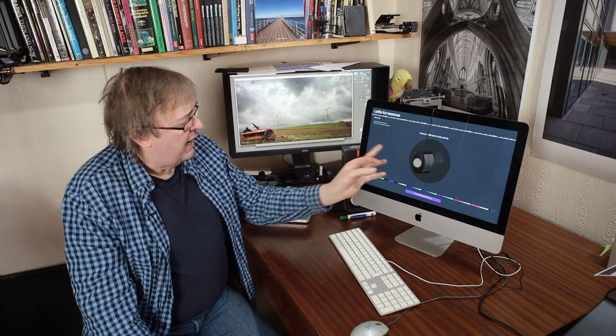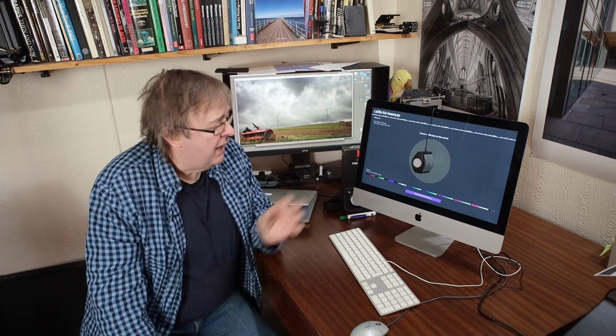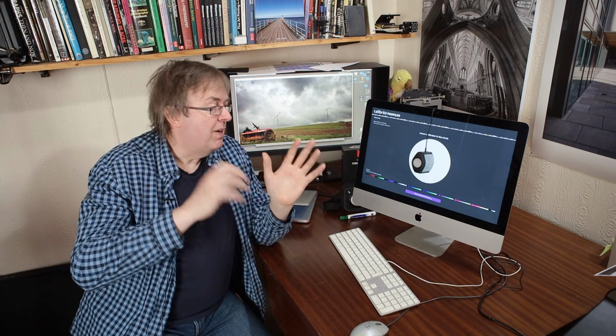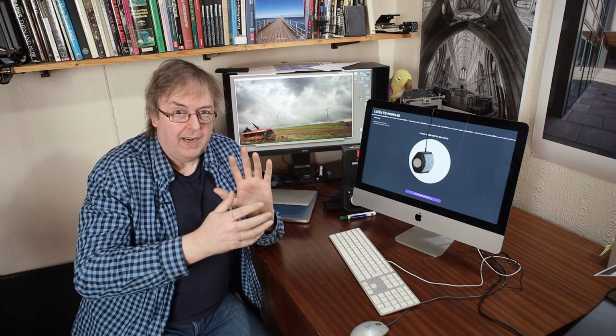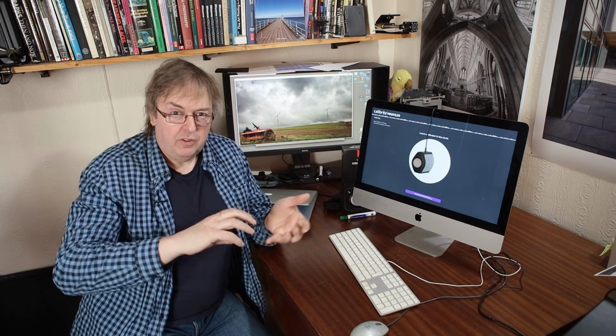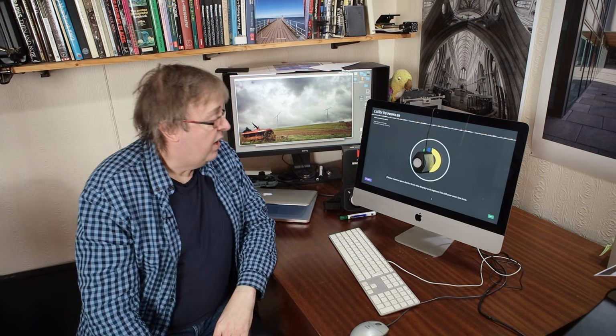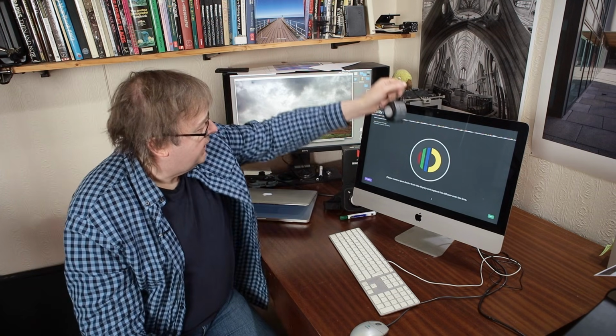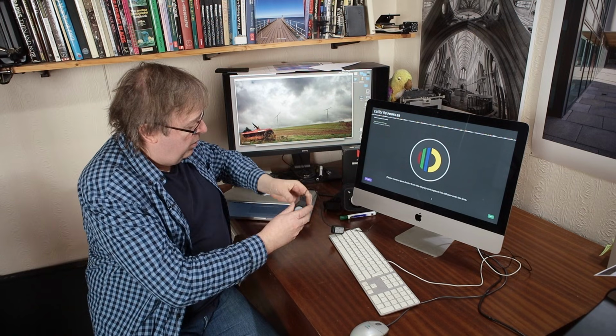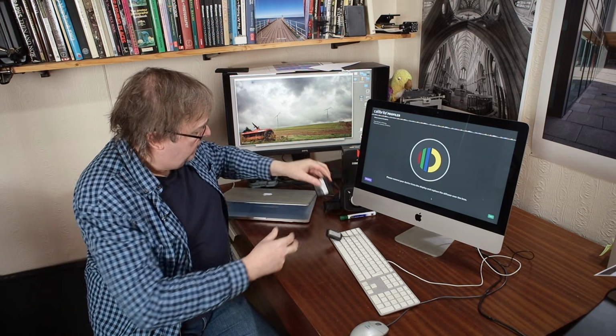Runs through, it ends off with a grayscale adjustment. Effectively, the software is displaying colours. It's then measuring what the actual colours of the screen are. It's using that difference between what it's sending to the display and what the display is producing to calculate the profile. So there we go, it says it's done. I can take that off, put the cover back on there.